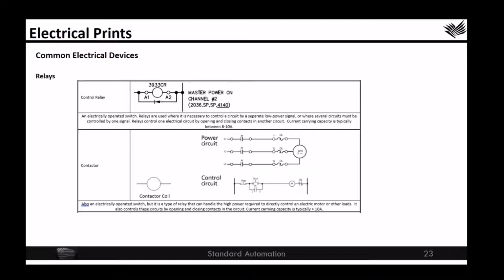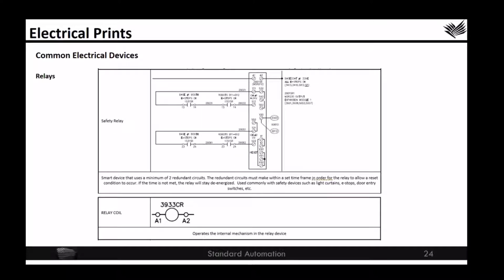Contactors are also an electrically operated switch, but it's a type of relay that can handle the high power required to directly control a motor. We also have safety relays. Safety relays are smart devices that use a minimum of 2 redundant circuits. The redundant circuits must make the same connection within a set time frame in order for the relay to allow a reset condition to occur. If it's not met by both channels in that time frame, the system will stay de-energized. Usually this is used with safety devices like the light curtains, e-stops, door entry switches, things like that.